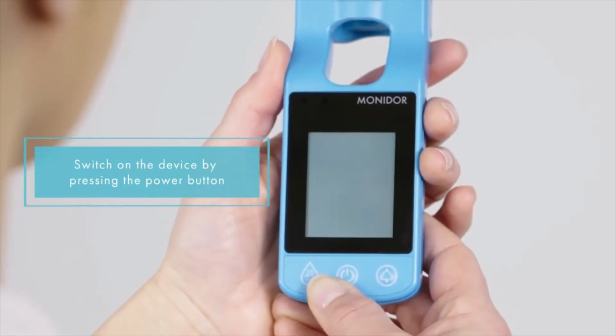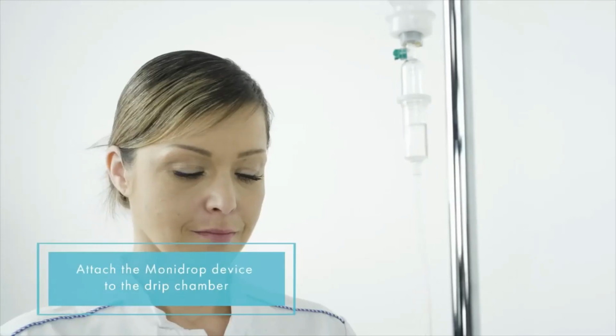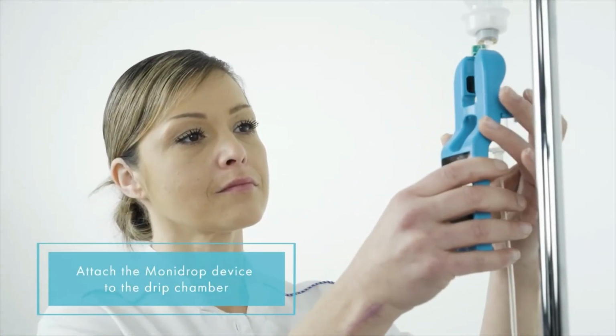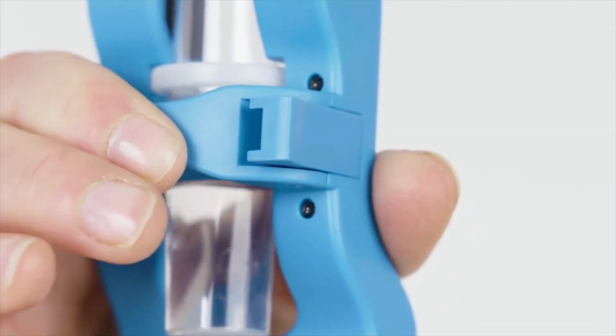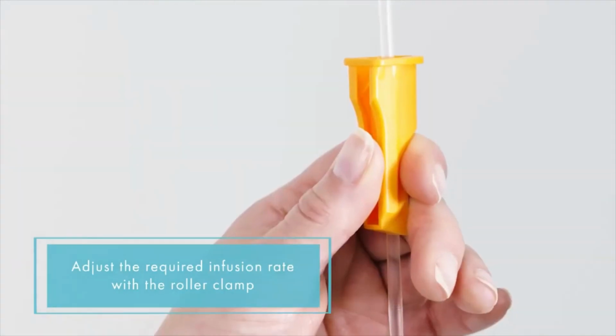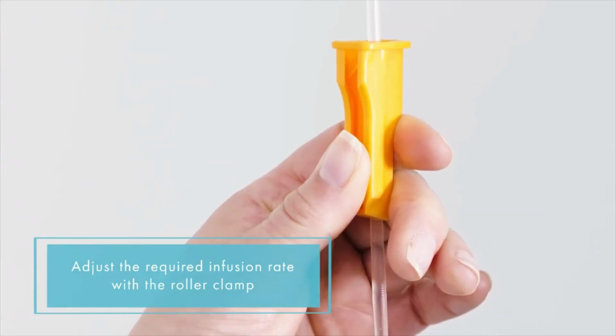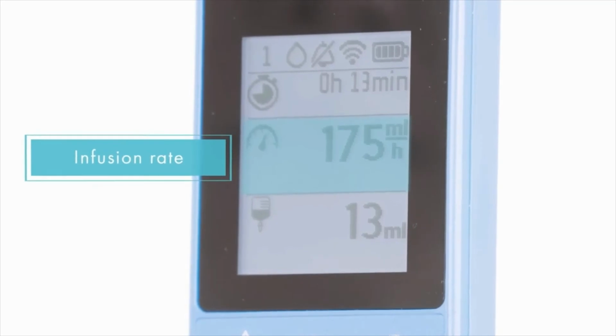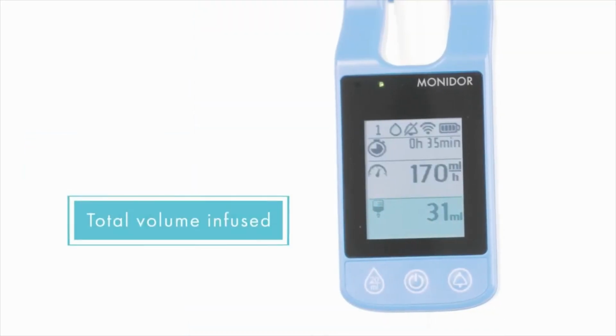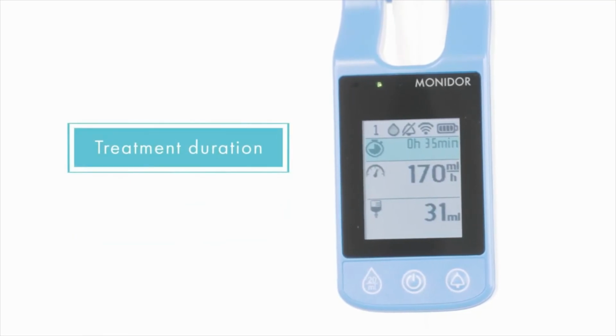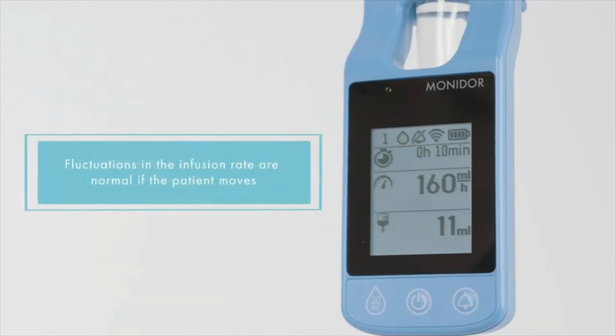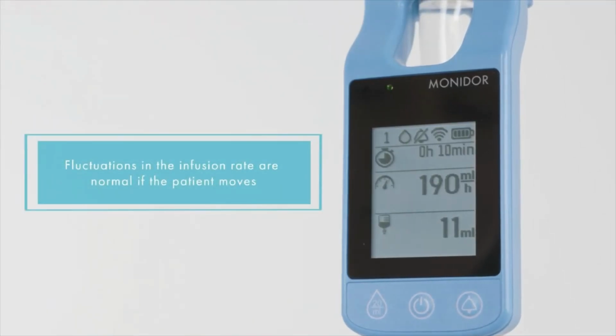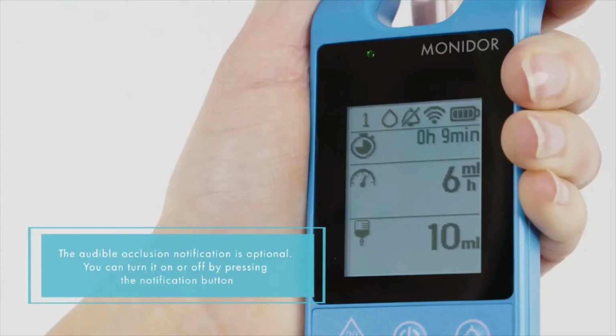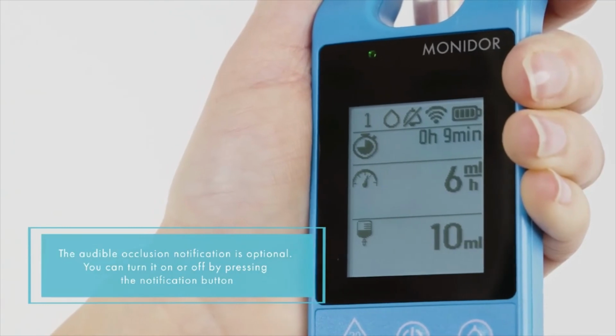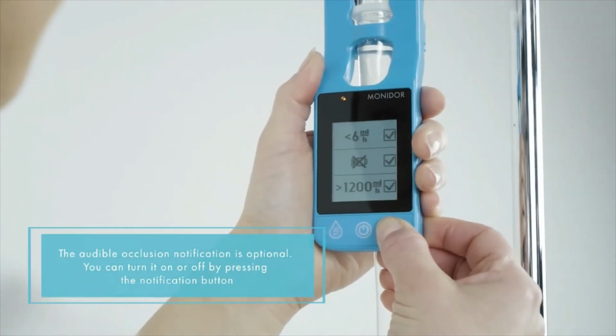switch on the device by pressing the power button. Attach the Monidrop device to the drip chamber. Adjust the required infusion rate with the roller clamp. The device displays the accurate flow rate. The Monidrop displays the total volume infused and the total treatment duration. The Monidrop device doesn't adjust the infusion rate. Fluctuations in the infusion rate are normal if the patient moves. The audible occlusion notification can be turned on by pressing the notification button.